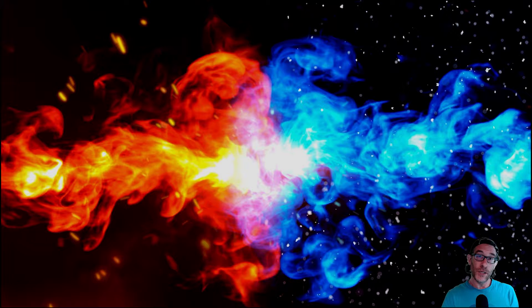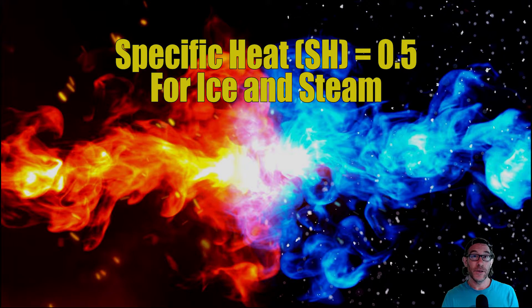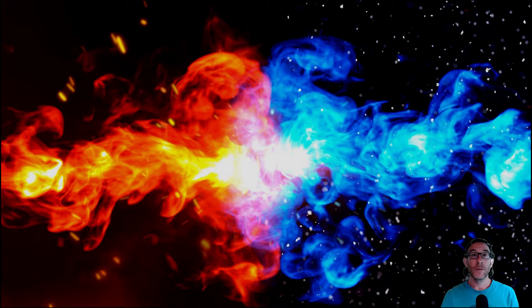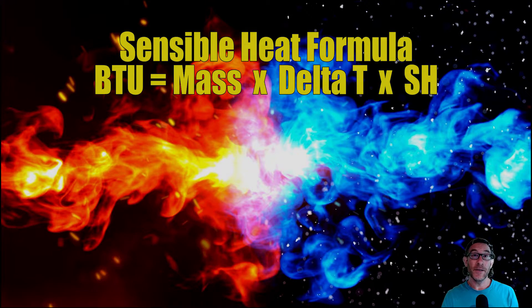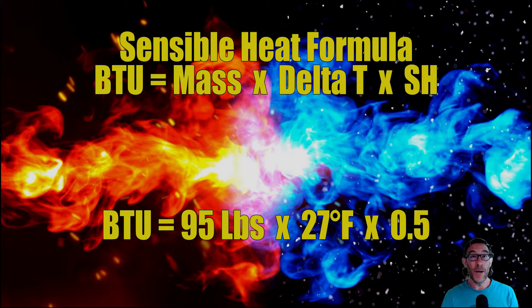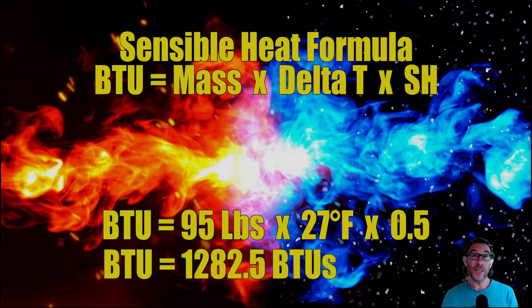There is one more important piece of information we need before the calculation: the specific heat capacity of ice, which is 0.5 — incidentally the same as steam. Now we plug all these numbers into our BTU formula, which is mass times delta T times specific heat. So we have 95 pounds times 27 degrees Fahrenheit times 0.5. To heat this block of ice up to its melting point, we will consume 1,282.5 BTUs. Let's write that number down, because we'll need it at the very end.